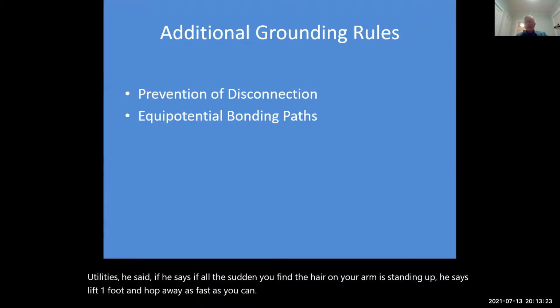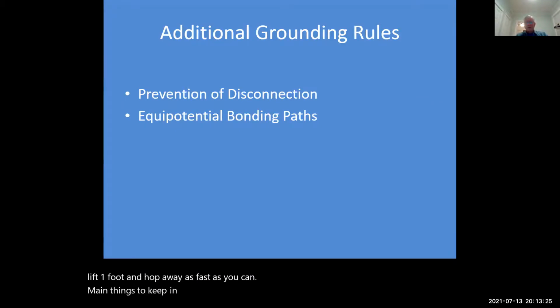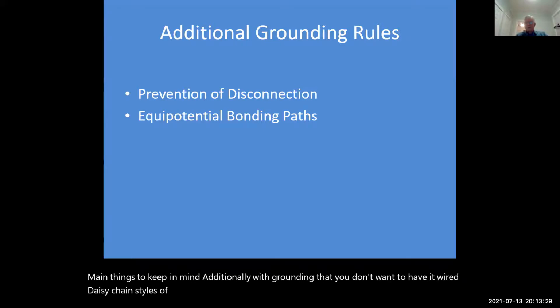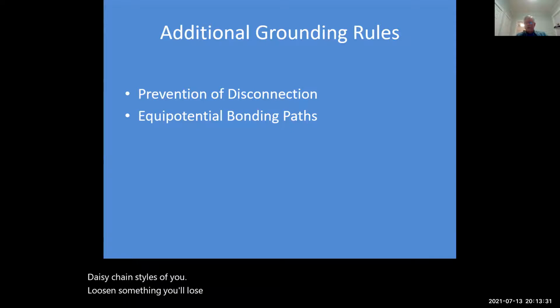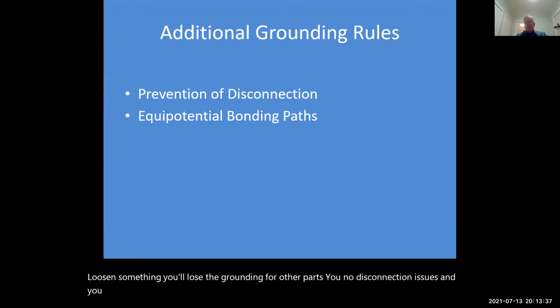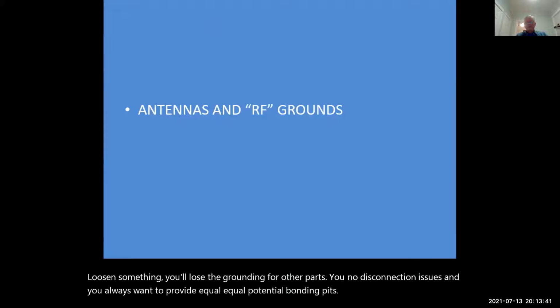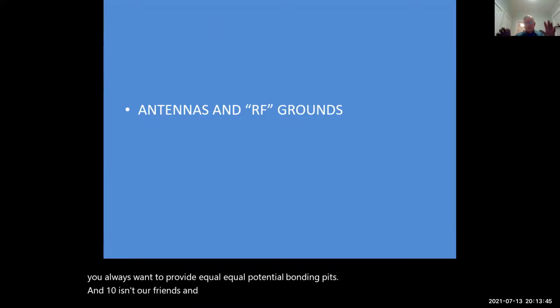Main things to keep in mind, additionally, with grounding: you don't want to have it wired daisy chain style. If you loosen something, you lose grounding for other parts. No disconnection issues, and you always want to provide equipotential bonding paths. Antennas and RF grounds, and again, this is all related to safety, not RF and antenna performance.